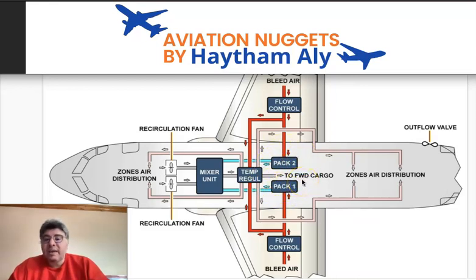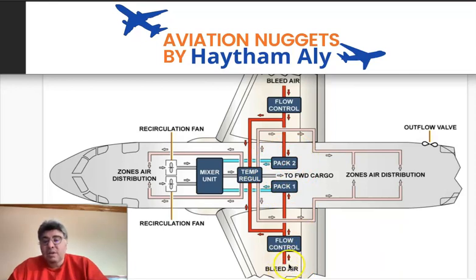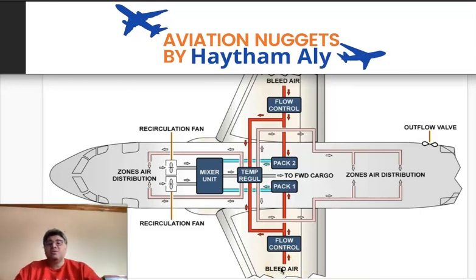The packs get their air from the bleed air system — Chapter 36. The bleed air is one of the users for the air conditioning packs. Air comes from the high-pressure compressor of the engine, regulated in terms of pressure and temperature before supplying the packs. However, this bleed air is still very hot and at high pressure — even after the pre-cooler, it can be around 150 to 200 degrees Celsius.